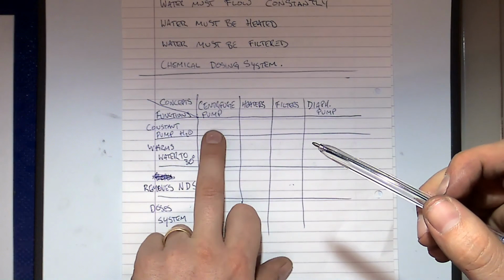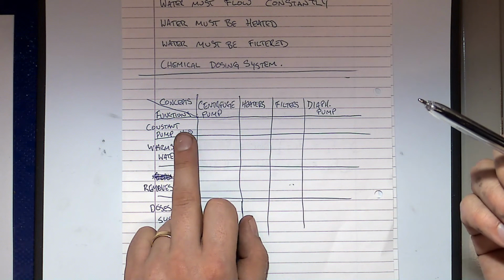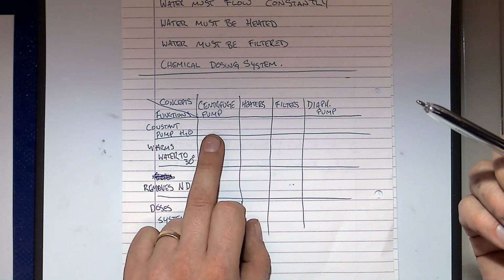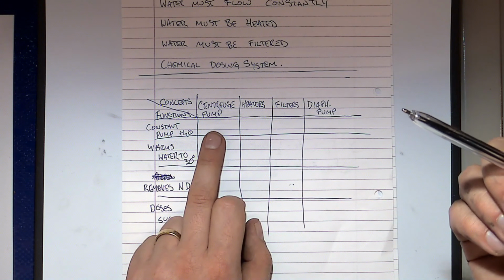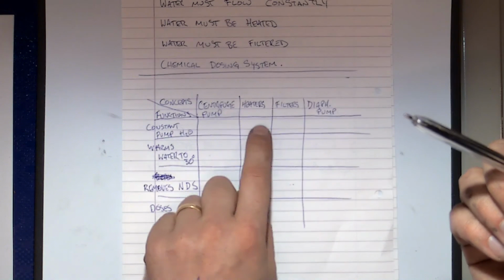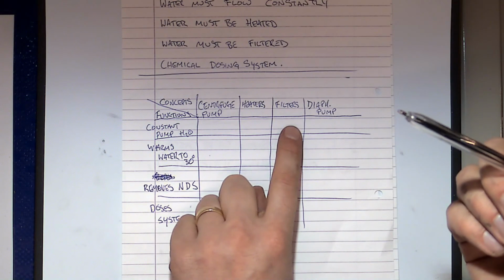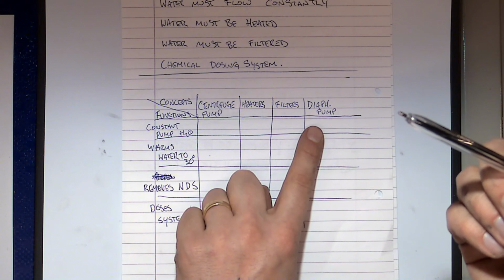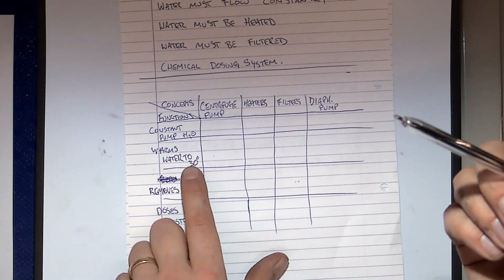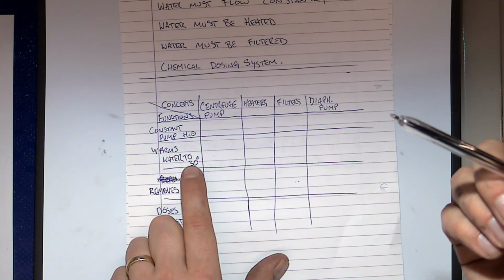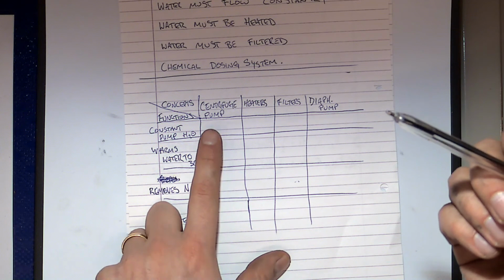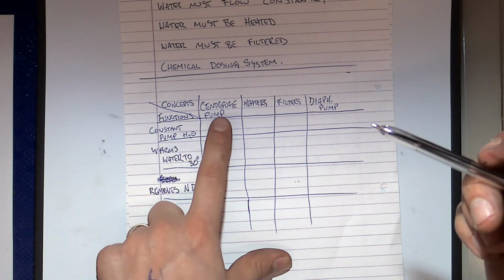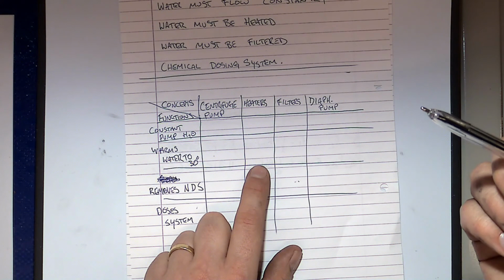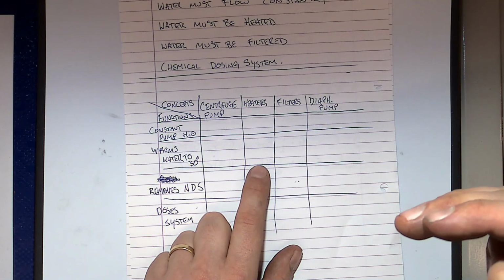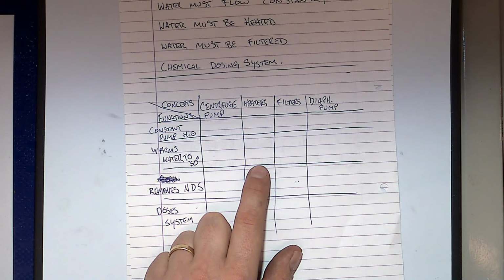So, in here, centrifuge pump, constant pumping of H2O. That pump needs to be able to pump the water through the heaters, through the filters, and still allow the diaphragm pump to dose. So these are all things to consider. The water's at 30 degrees, so we need to be sure that, okay, that's not very hot, but if it were a higher temperature, the centrifuge pump can handle that. The heaters themselves need to be able to cut on and off to maintain, so there needs to be a temperature checking device.